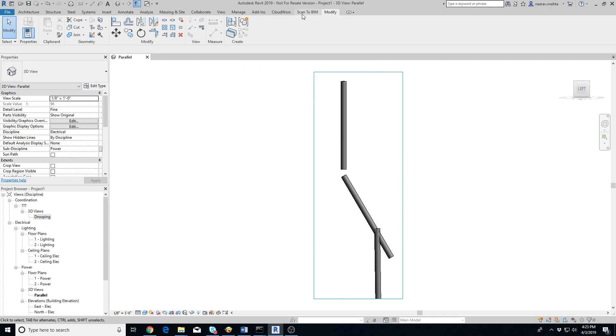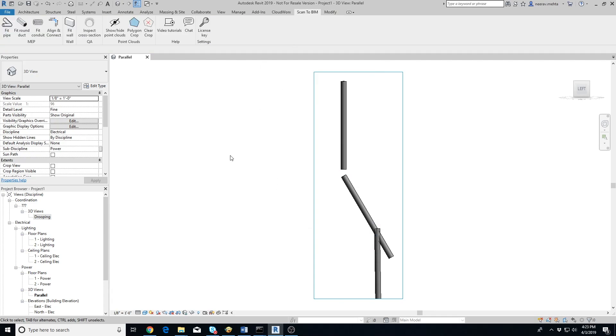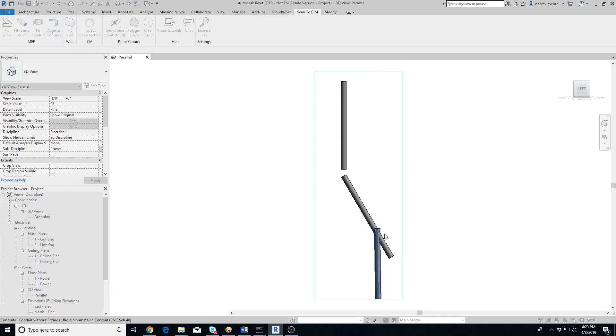If the fittings are not defined, you will first need to load the appropriate families in Revit and configure them. To connect the conduits, click the Align and Connect button, then select all the conduits in a run that you want to connect. Make sure to select them in the same order in which they are supposed to be connected — conduit one will connect to conduit two, conduit two will connect to conduit three, and so on.